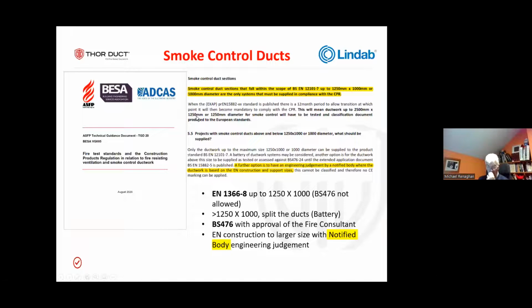When it comes to smoke, all smoke ducts up to 1250 by 1000 have to by law be EN. There's no give on that. You may not use BS. Where the duct is greater than 1250 by 1000, the first option is to redesign the ducts down to 1250 by 1000. Where that can't be done because of air volumes, etc., split the ducts, so you have what we call a battery. The third option after that is to have BS 476 with the approval of the fire consultant. So he has to sign off and say that that's the right route to go.